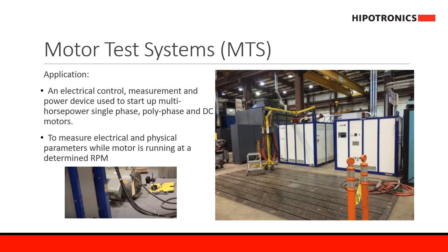Another great solution we offer here in Hipotronics is the motor test systems. The MTS is an electrical control, measurement, and power device used to start up multi-horsepower single-phase, polyphase, and DC motors. The MTS measures electrical and physical parameters while the motor is running at a determined RPM.